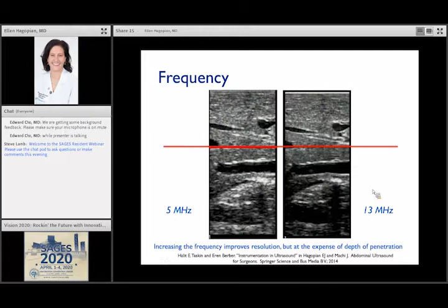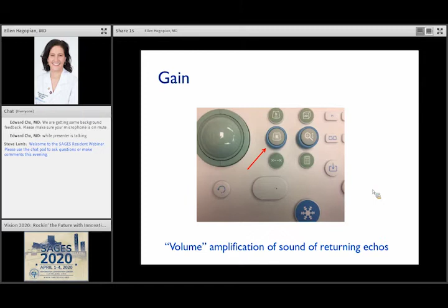So gain, if you had one word to think about with gain, it's really volume. It's like turning up your radio. It's volume amplification, and it's volume amplification of the returning echoes. So remember, we talked about what's emitted from the ultrasound probe is actually power, but most of the probe's time is spent not emitting ultrasound waves, but listening, and that's what gain is.